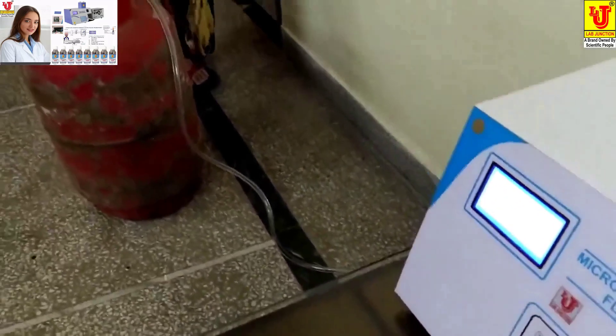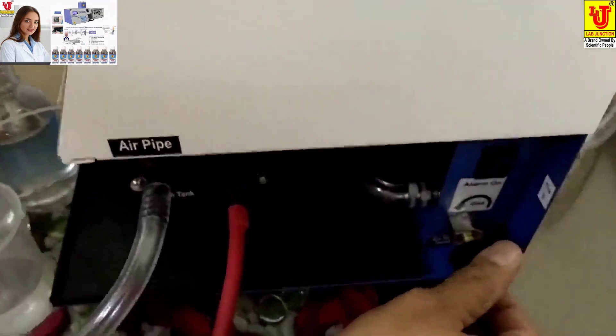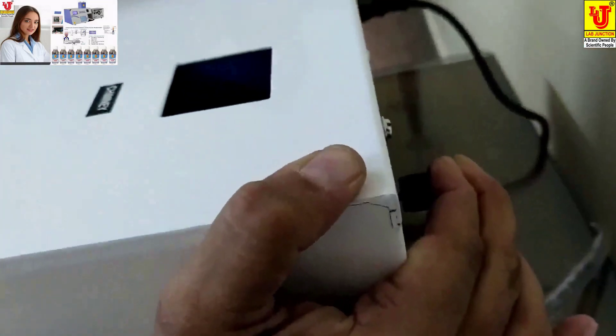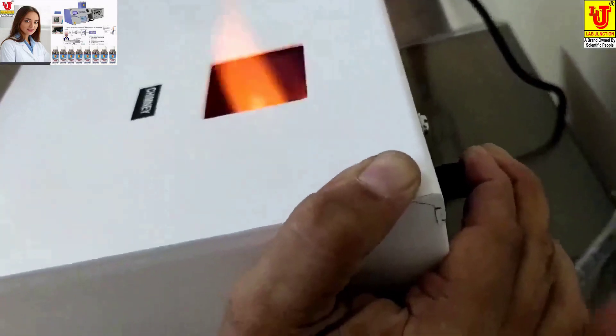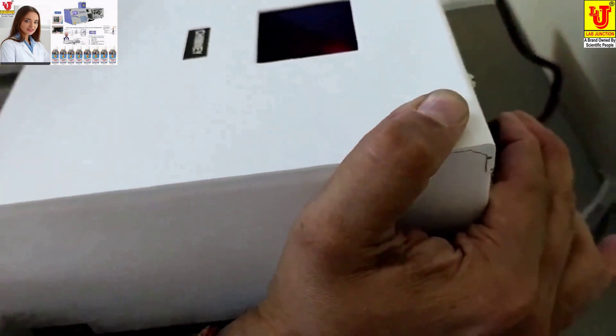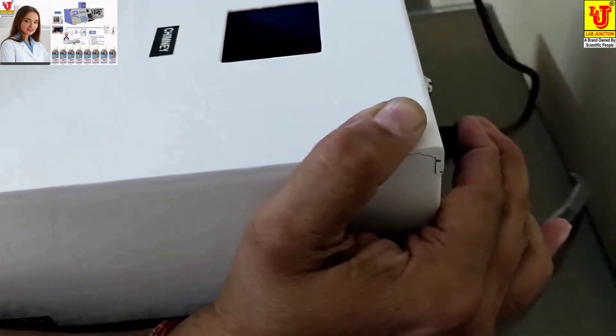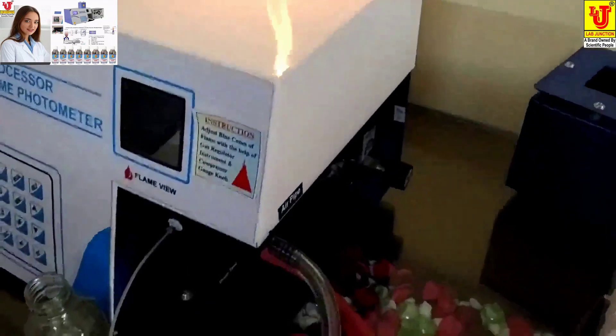Now switch on the gas. Slightly move one rotation only, and press the manual ignition on the back side of the unit. Now the flame has to be set — let's see how to make it perfect.